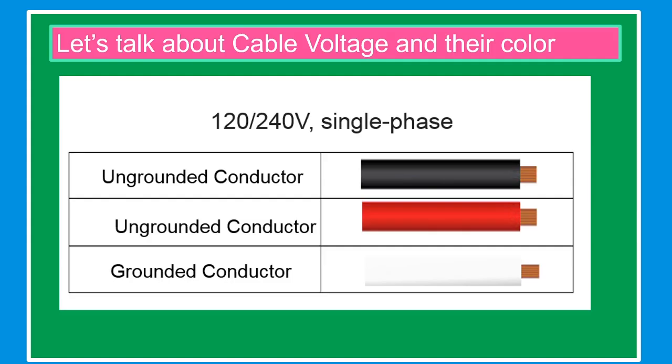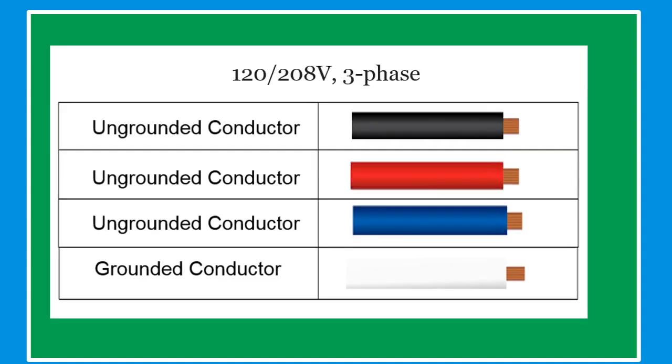Let's talk about cable voltage and their colors. For 120-240 volts single phase: ungrounded conductor color is black and red; grounded conductor color is white. For 120-208 volts three phase: ungrounded conductor colors are black, red, and blue; grounded conductor is white.